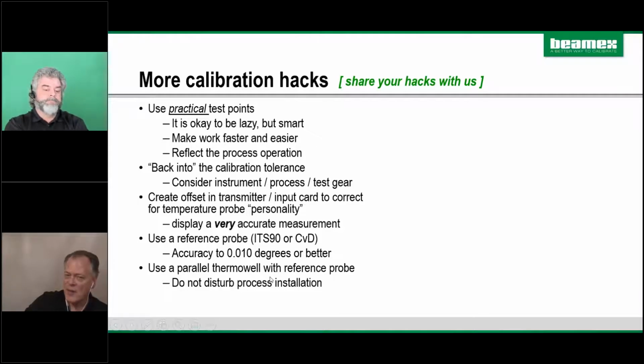Sometimes it's not easy to pull the probe out of the process. It could be mounted in a weird place, or it's all corroded, and to actually remove that field probe would cause more harm than it's worth. So another consideration is to install a thermal well right next to the probe. Heat treating people with furnaces do this all the time. You can just walk up to that thermal well, stick a thermometer that's traceable to NIST in there, and compare the process reading to your field thermometer. It costs some money to do that, but it can save you a lot of time and headache and allow you to verify that things are running well.